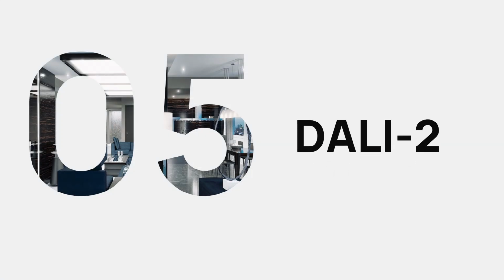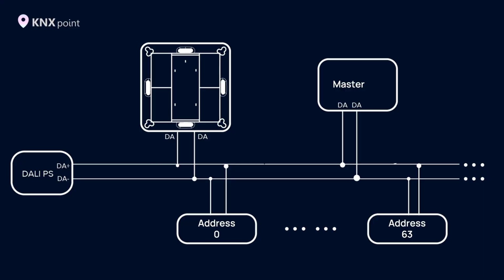DALI 2, an extended version of the DALI protocol. In the DALI 2 system, a new type of command called events has been added. These commands are sent by control devices to a special event controller. The controller will send regular commands to actuators based on settings and loaded scripts.